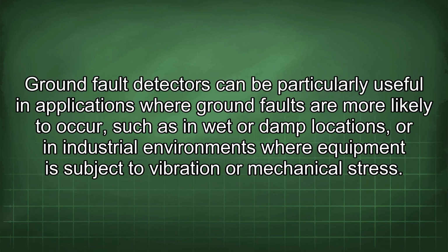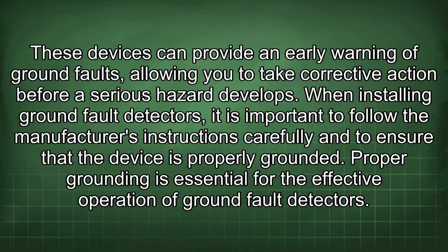Ground fault detectors can be particularly useful in applications where ground faults are more likely to occur, such as in wet or damp locations, or in industrial environments where equipment is subject to vibration or mechanical stress. These devices can provide an early warning of ground faults, allowing you to take corrective action before a serious hazard develops. When installing ground fault detectors, it is important to follow the manufacturer's instructions carefully and to ensure that the device is properly grounded. Proper grounding is essential for the effective operation of ground fault detectors.